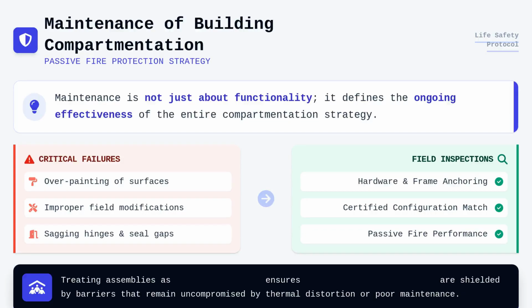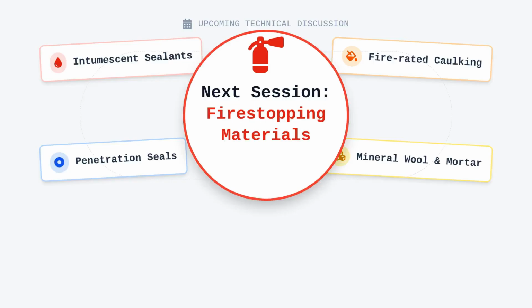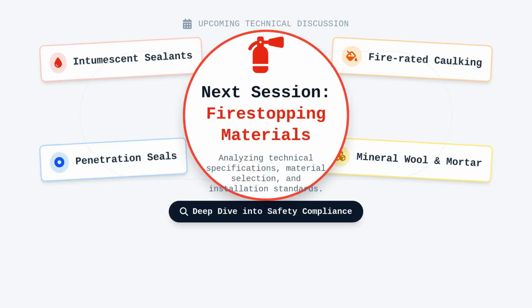We must treat these assemblies as living components of the safety system that require periodic verification to function flawlessly under extreme thermal distortion. This systematic approach ensures that firefighters and building occupants are shielded by effective barriers that have not been inadvertently bypassed by poor maintenance or unauthorized changes. I look forward to discussing the specifics of fire-stopping materials in our subsequent session.